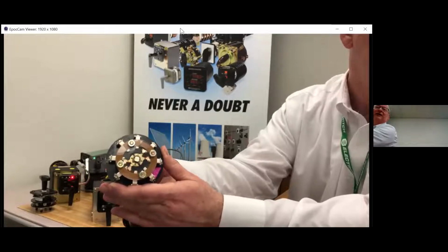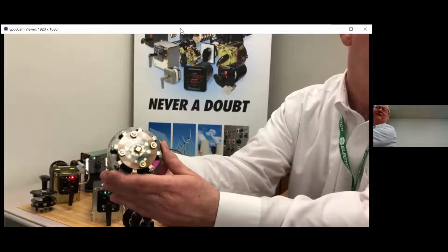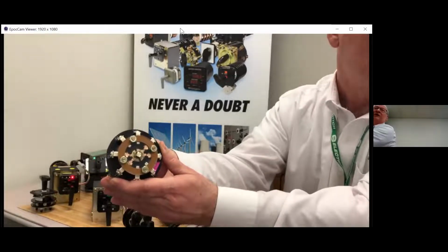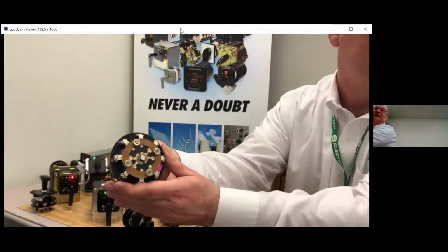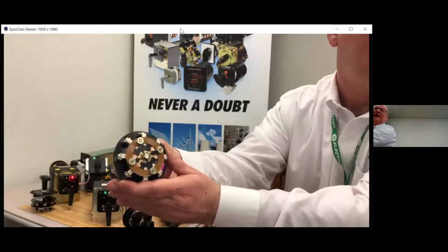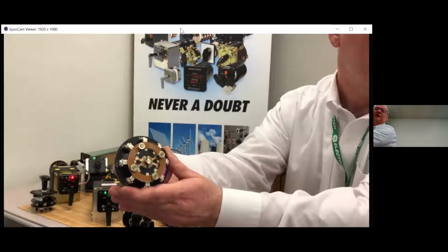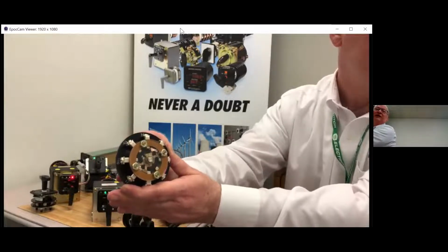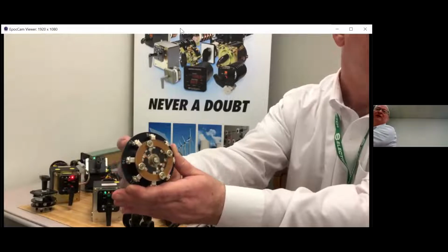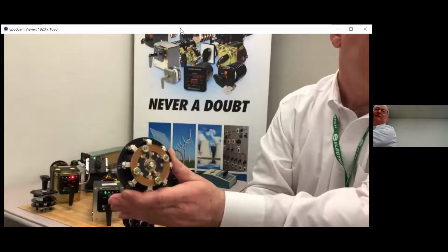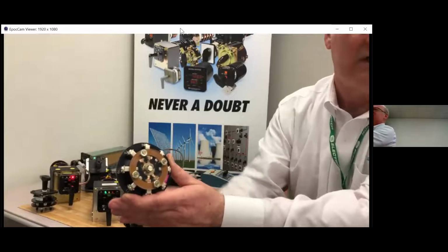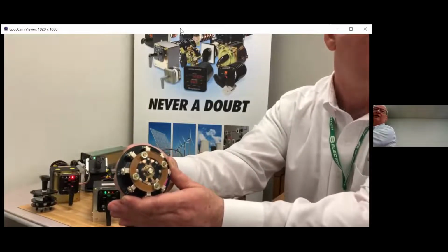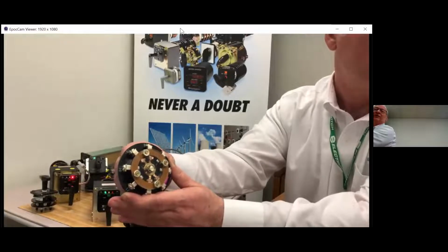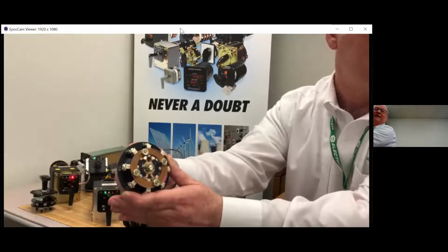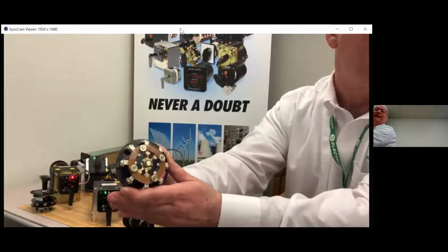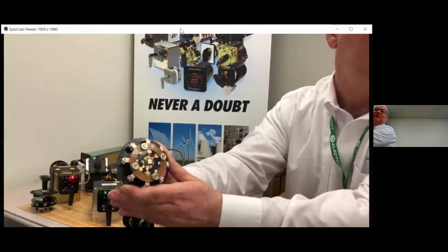And this essentially allows me to give multiple contact configurations on the same deck, which gives me 2 normally open and 2 normally closed contacts for every deck on the back of a Series 24 switch. So you can see how that rotates and opens and closes contacts. Without getting too complex about the switch, these contacts right now are considered break before make. So as I rotate the switch, I'm breaking the contact, and then there's an air gap, and then I'm making it again in another situation, another circuit.